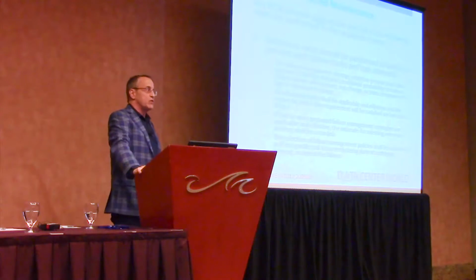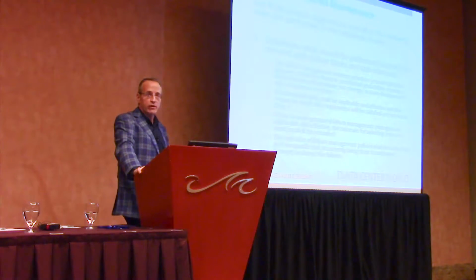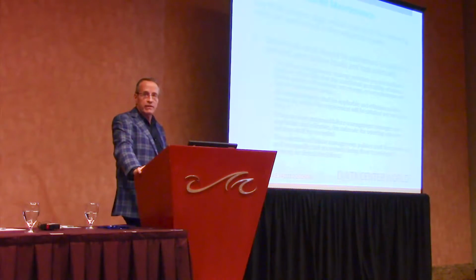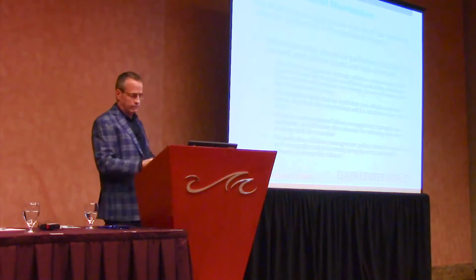Now we decide what to do about those failures. If they're hypercritical, we do a lot; if they're not so hypercritical, we don't do so much. We found stuff like we were changing our generator oil too often -- if it only has 40 hours on it, no metal shavings, no water buildup, carry on.